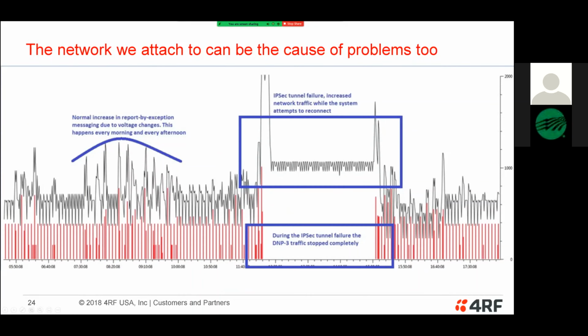They were using IPsec, and they had a network diagnostics tool that would poll every Ethernet device in the system at noon every day. It didn't pace out those polls - it did a massive blast of like 3,000 polls in less than a second from the network management system. When it hit the SCADA network, it would take the network off the air because the IPsec tunnels would collapse, and once collapsed, they had a hard time reconnecting until somebody recycled the router.